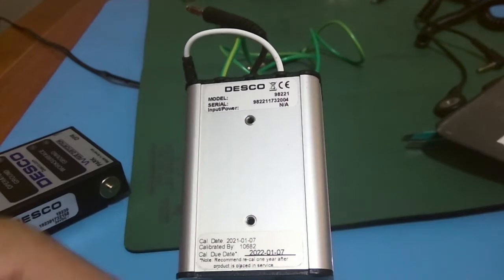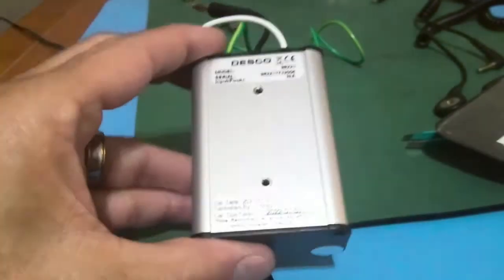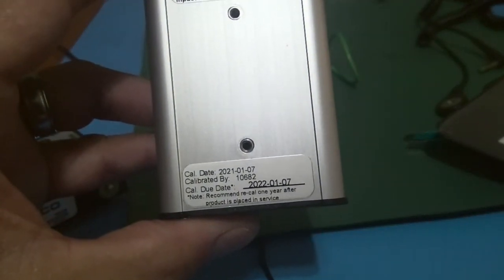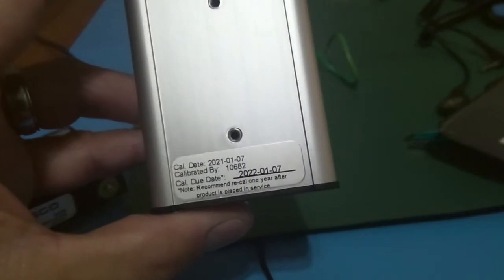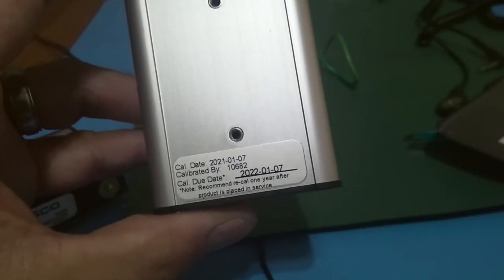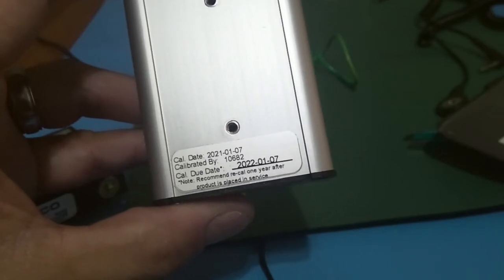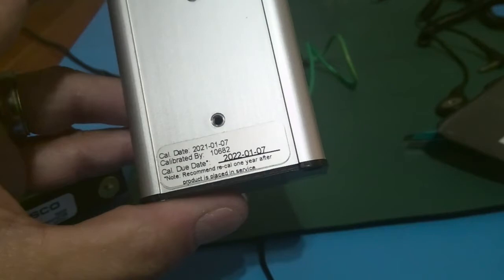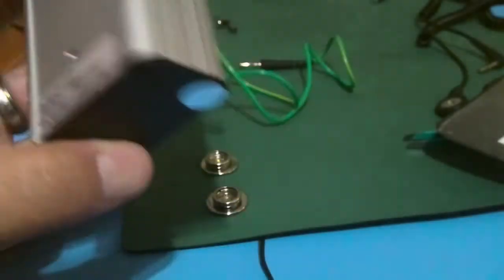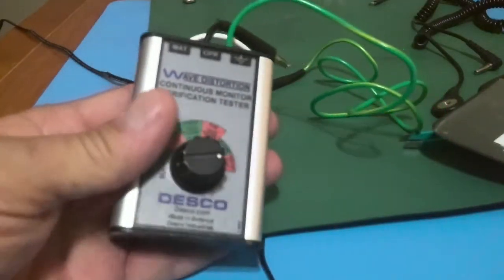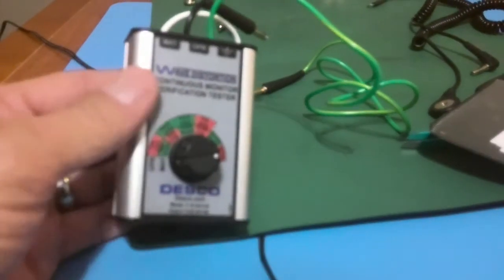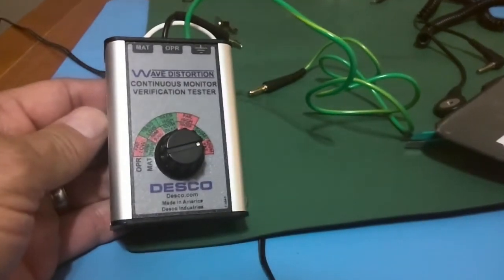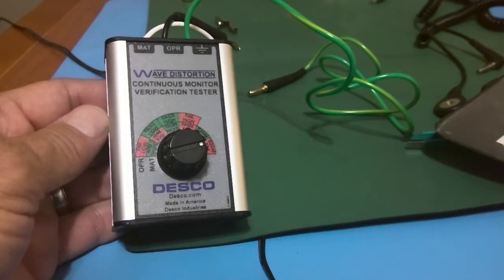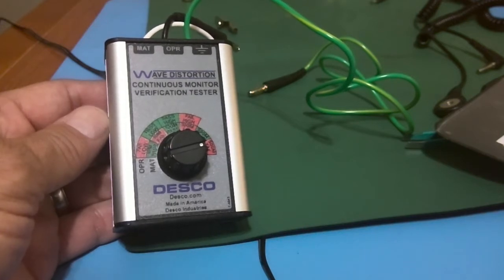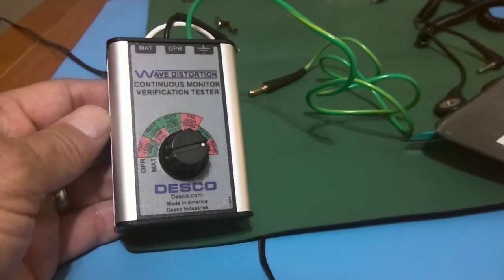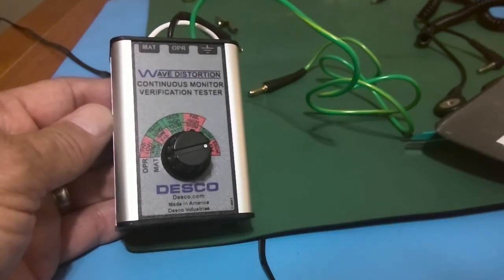The DESCO calibration unit also needs to be calibrated. So you've got to make sure that you send this back to DESCO at least once a year, near the calibration date that's on your sticker, and have them recalibrate it. It has to go to the factory for recalibration. What you'll do is contact customer service at DESCO, and they'll give you return authorization paperwork. You'll send that in with the monitor. They'll give you a price up front, and if anything changes on the price, they'll let you know before they do the work.